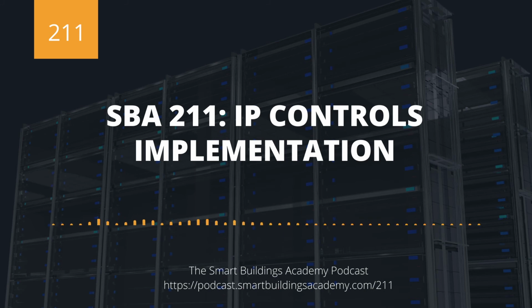So how I would architect this is I would put an Edge 10 or Edge 30, depending on my IO count and what compute capacity I needed, or something similar to that. I'm just using that because that's a very common product, and Niagara has a large market share, so most people know what it is. But it could be similar. And so once you put that in place, then you run your field controllers off of the field trunk, wire them up, and you're good to go. And that's it. Pretty low cost implementation strategy that you can do all day that will keep your costs down and is pretty easy to implement.